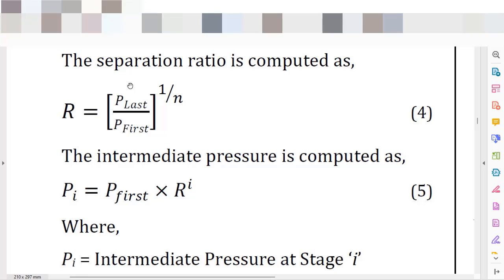The absolute pressure, just to remind you, is the sum of manometric pressure plus the barometric pressure. Barometric pressure is a function of the elevation of your site — the higher the elevation, the lower the barometric pressure. The manometric pressure is the pressure most often read on the manometer or pressure transmitter of your system; it is the difference between absolute pressure minus barometric pressure.